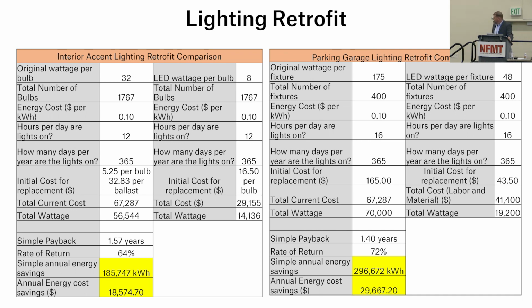So we took the parking garage. We put a total cost, with labor, on the right. In the parking garage we took 400 fixtures at 175 watts, the big metal halide ones that run hot and burn up, and changed the whole fixture to a 48-watt T5 high-efficiency LED lamp. Doing that for all 400 fixtures, going from 175 watts to 48, you're looking at a savings in the garage of almost 300,000 kilowatt hours annually. So your payback is less than a year and a half.